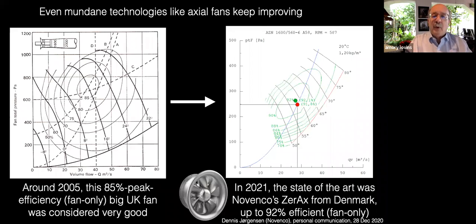And of course, technologies keep improving. A generation ago, a great fan for distributing lots of air in a big building, like the one I showed 2 slides ago, might be at best 85% efficient and come with a motor with an efficiency rating called IE3. Now it can get 92% efficient with a big bullseye on the right at very high efficiency, and it can come with a variable speed IE5 motor, better. That's in this case 93.1% efficient, and better motors still to come. More on motors later.